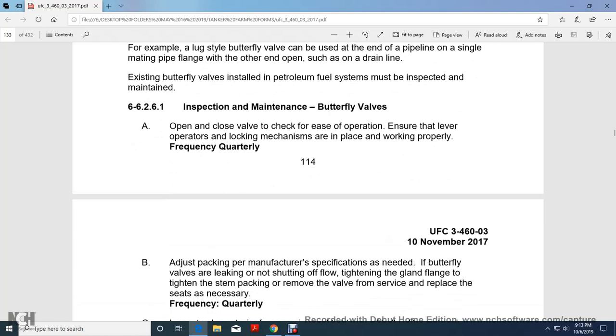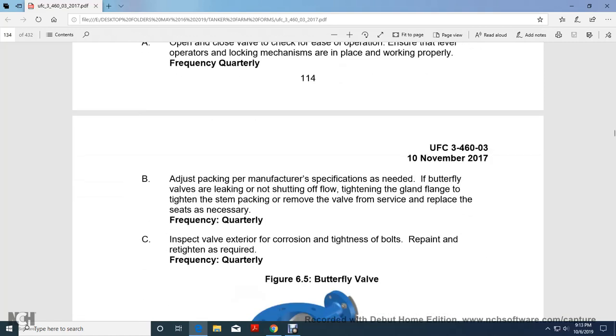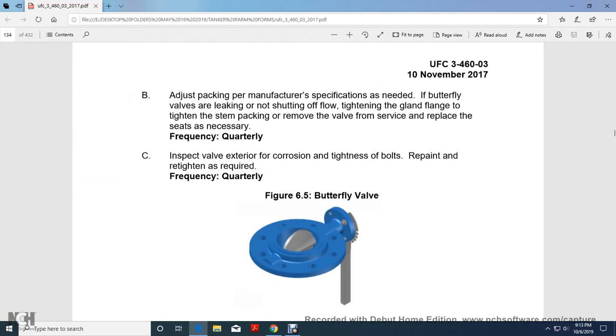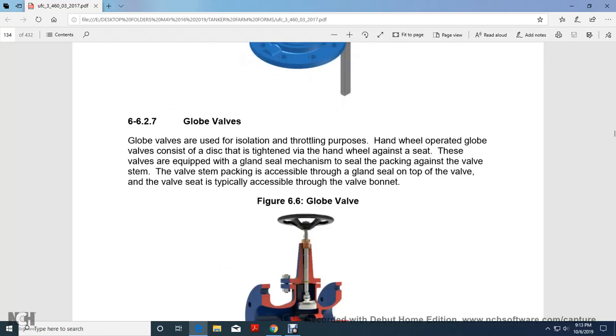Inspection and maintenance of butterfly valves: open and close the valve and check for ease of operation. Check that the lever operates and the locking mechanisms are in place and working properly, quarterly. Adjust packing per manufacturer specifications as needed. If the butterfly valve is leaking or not shutting off flow, tighten the gland flange and the stem packing, or remove the valve and repair the seat surface as necessary, quarterly. Inspect the valve exterior for corrosion and tightness of bolts, repaint and retighten as required, quarterly.